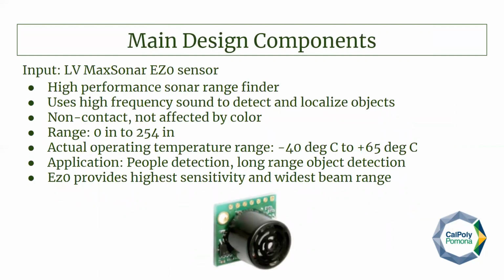As mentioned before, the EZ0 sensor is the input that measures distance. It works by transmitting a high-frequency sound and measuring the time for it to be reflected back, then converting that to distance. A major reason we chose this sensor is that its range goes beyond what we need to detect, specifically up to 254 inches, approximately 21 feet. The operating temperature covers a wide range that was later tested. The sensor is also known to be used for detecting people and for long-range detection. Out of the entire EZ series, the EZ0 offers the highest sensitivity for the user and can detect objects at a wider range.